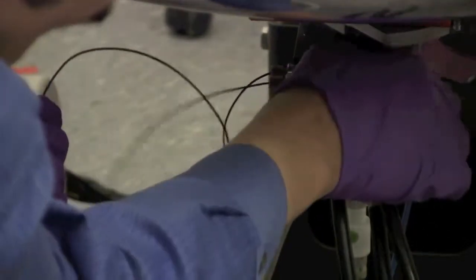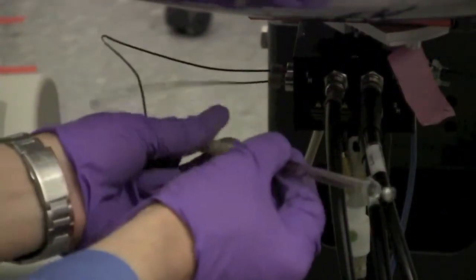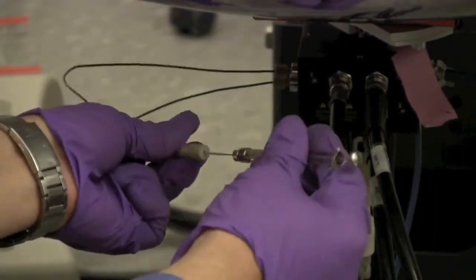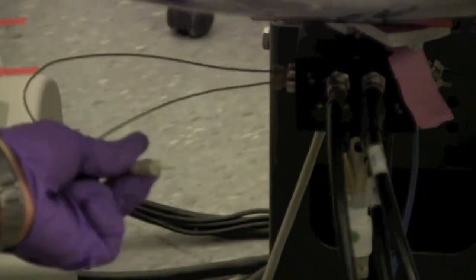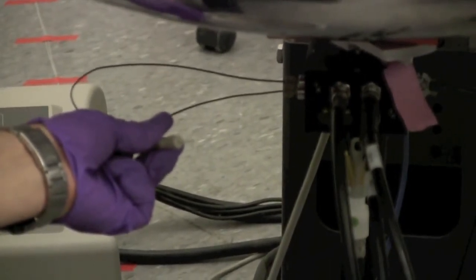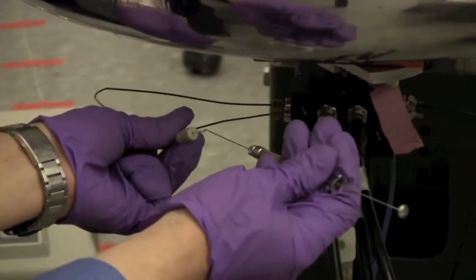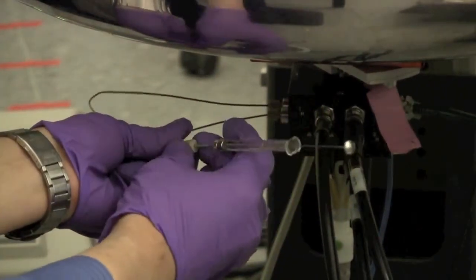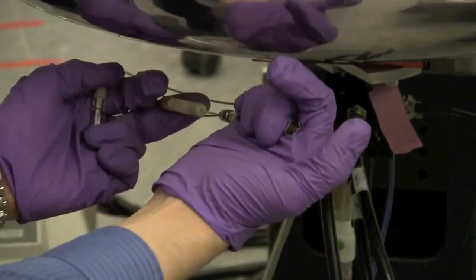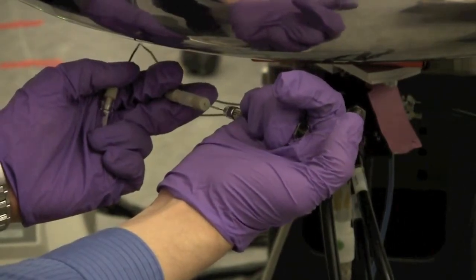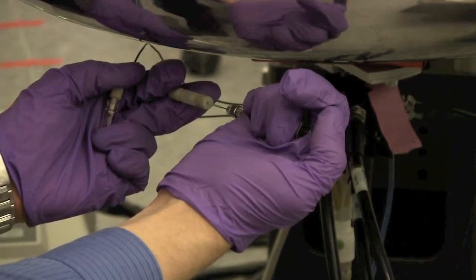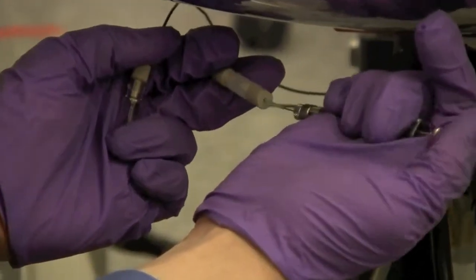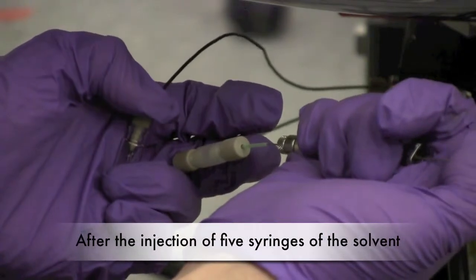I'm going to get the syringe out, loosen it, and I'm going to draw it up with some clean solvent. And you'll want to probably draw up more than the 25 microliters you used before. I'm drawing about 50 microliters here. Put it in and go ahead and push it through. And if all goes well, you should see a bubble forming on the outlet. So now we've recovered our sample.